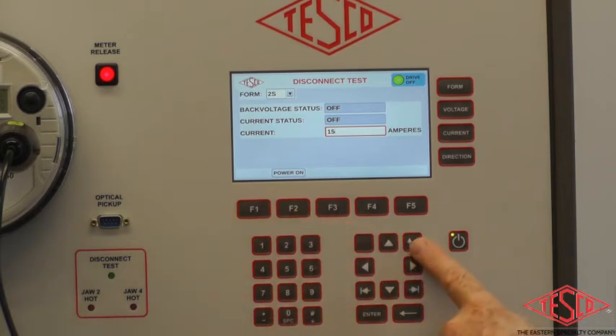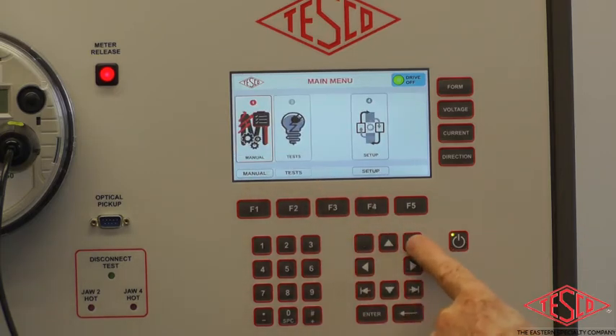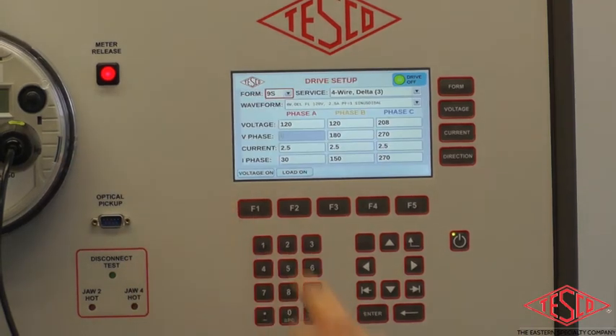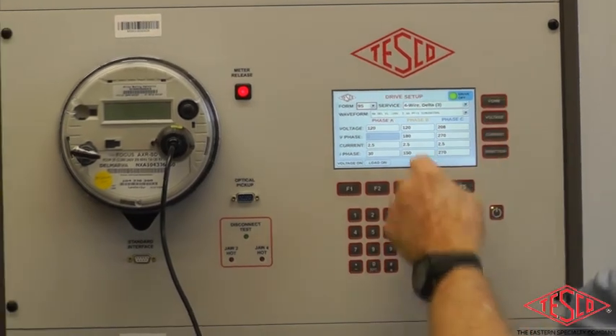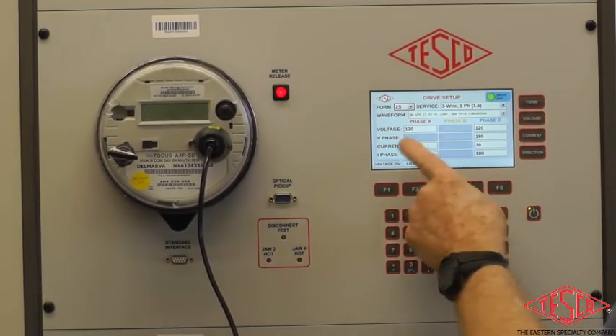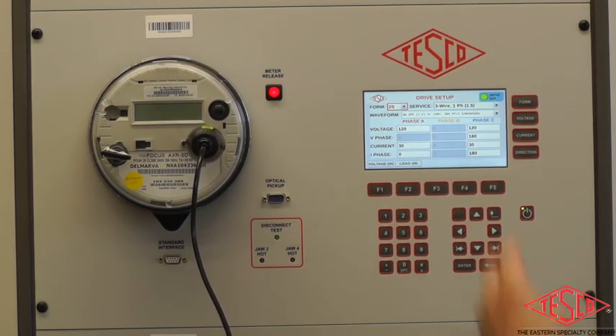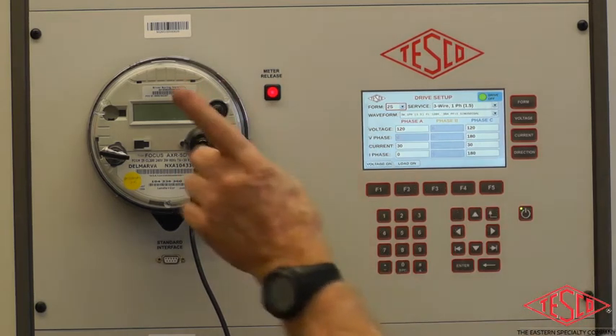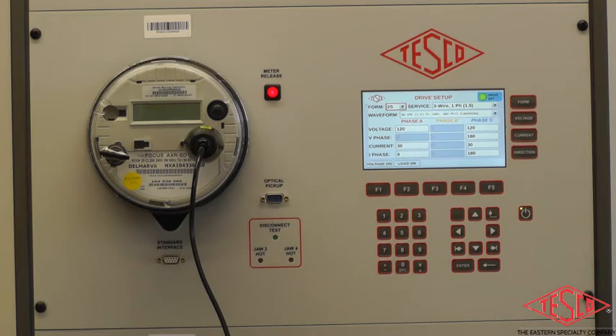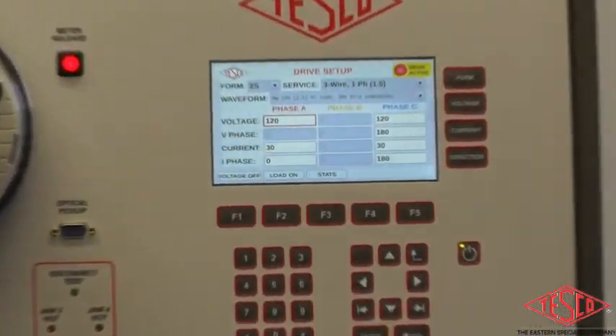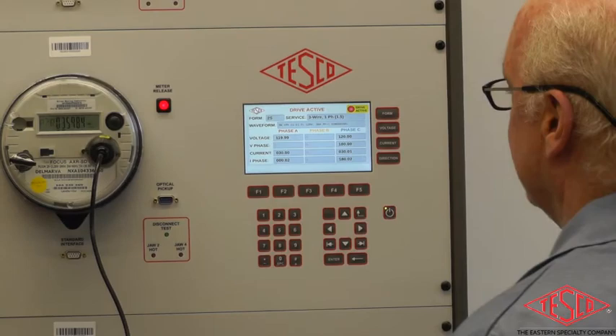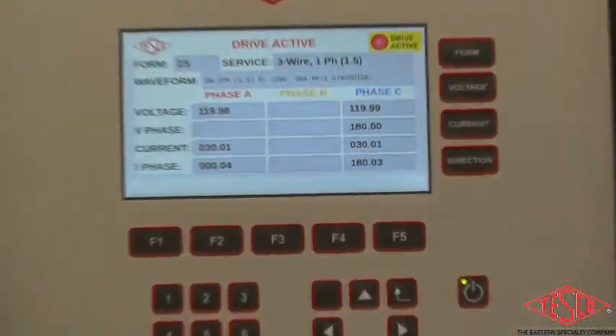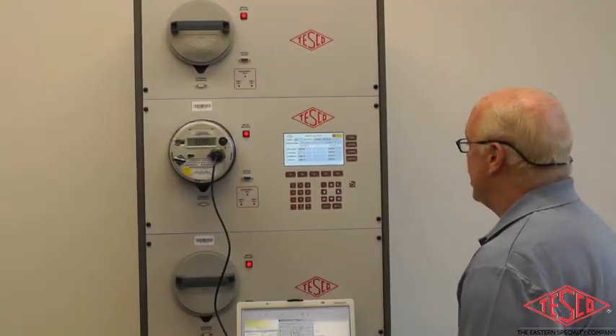So we'll go out of this. I'll show this back on the main screen. So always when you want to go to the higher menu, press this back key here. So then we go to the next one, and you're back to the manual screen. So for the Form 2S, go manual, press Form here. We get 2, press 2. If we want to do a voltage, now the way this does, this is actually a 3-wire. So it shows 120 and 120. Basically it shows 120 this way, 120 that way. So it's actually a 240, but it measures it as two 120s. But if you look, you will see that there's 240 in here. And you can also press load on. And if you go to stats, you can see the meter going forward. So that's basically the quick operational video of this.